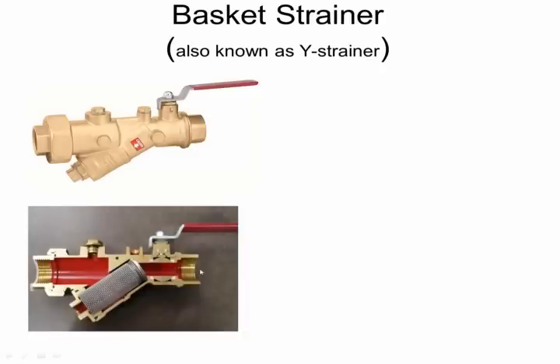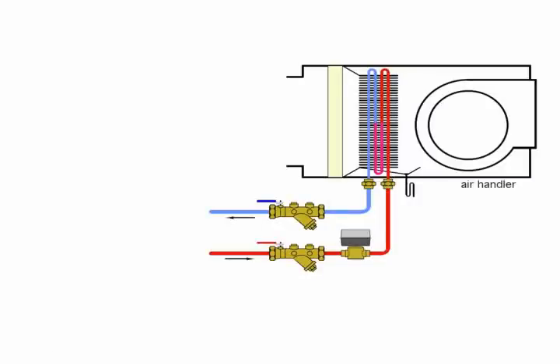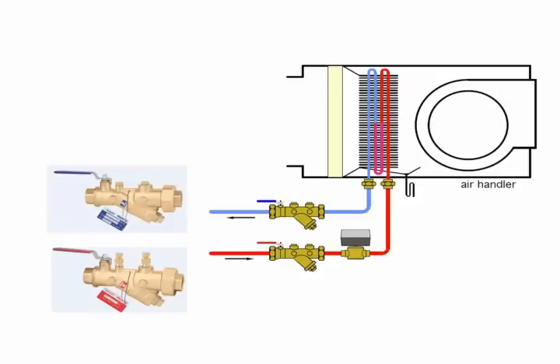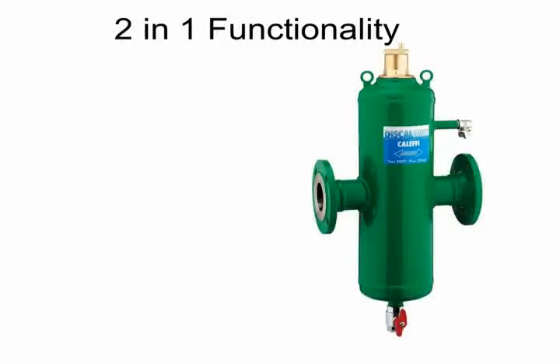Speaking of which, here's a Caleffi Y strainer or basket cartridge filter. We like these, but we like them high up in the system. And if you did a cross-section, this is what they look like. They have a little filter here, and fluid would come in this direction, go into here and back out here, and the debris would catch here. We like these high up in the system, such as air handlers and fan coils, because the higher up in the system you go in your building, the less chance of debris. Debris likes to live down in the bottom of your system largely. So they're a good place for using Caleffi or someone else's Y strainer, protecting this control valve and the heat exchanger on an air handler or a fan coil, combined typically with a balancing valve.